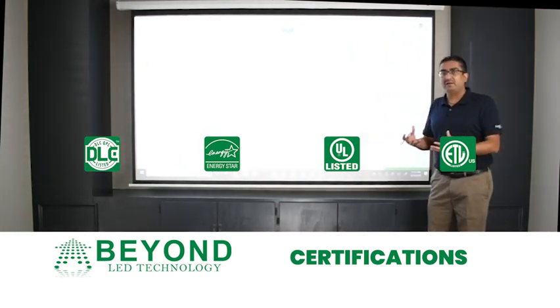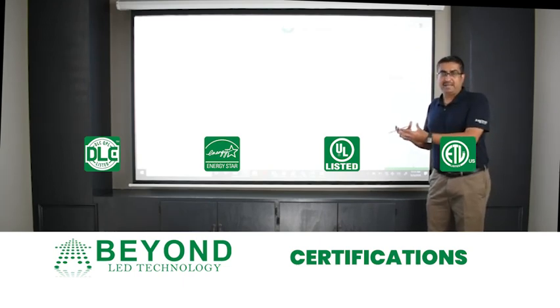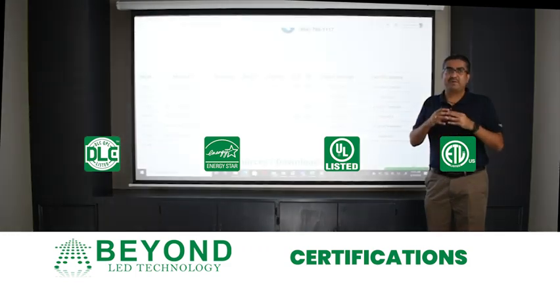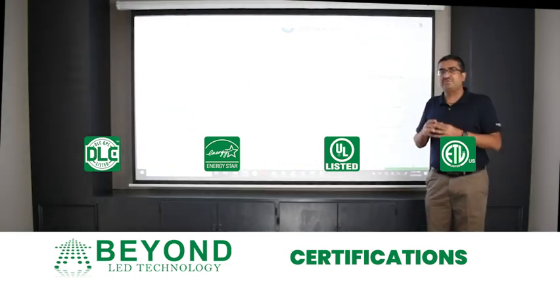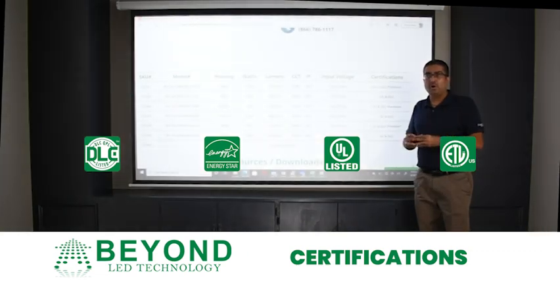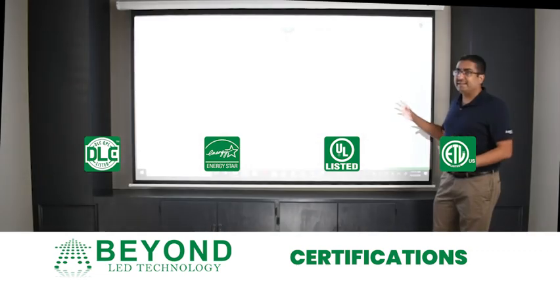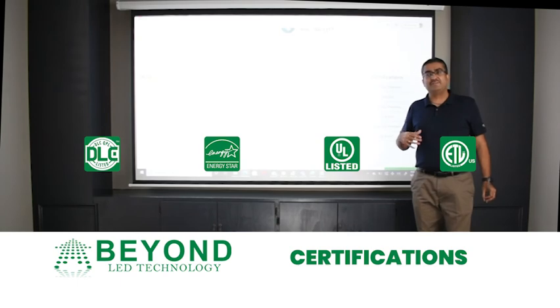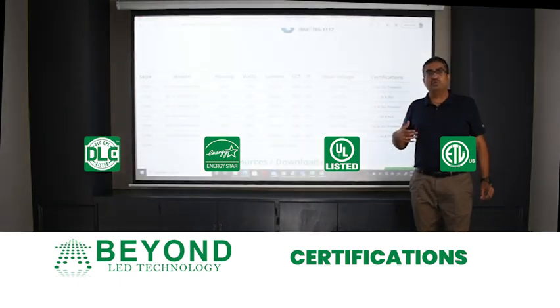It is required to install in North America. Any commercial and residential lighting product has to be either ETL or UL certified. And DLC and Energy Star are required to get the rebate from the power company.